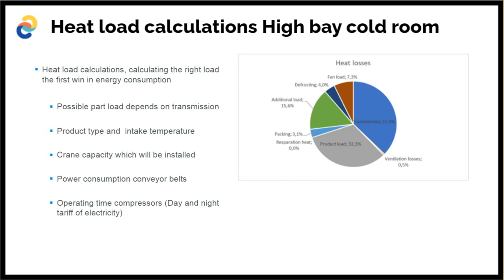And what's also an interesting one to look at is the operating time of the compressors. The less the compressors are running, the bigger they're going to be. But that could be a good solution, as I said earlier, that if there is a big difference in the tariffs, let them run at the cheapest time of the day, but make them a little bit bigger. But that's an investment you need to make, and it needs some calculation to find out if it pays back.